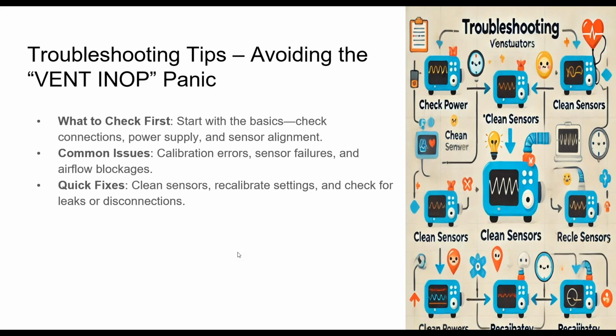Check your power supply, make sure that your red outlets haven't somehow lost power and you just switch over. I have actually had that happen before. Unfortunately, the backup batteries on that particular ventilator were rated to perform for another 45 minutes, but it causes this panic moment for clinical staff because they don't understand the technical parts. Typically, they don't need to worry about the technical parts, that they have about 45 minutes, give or take, to find another outlet. But I've literally run extension cords over to the nurse's station, and I've seen some hospitals that I've worked for have backup batteries that they can wheel in immediately if emergency power goes down.